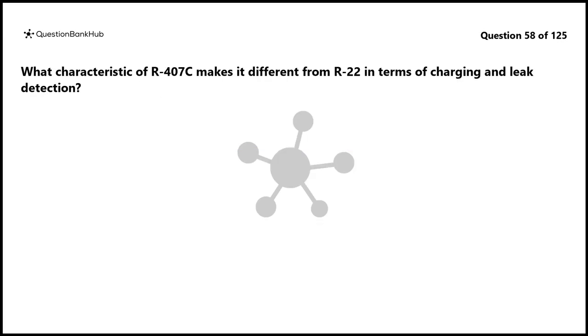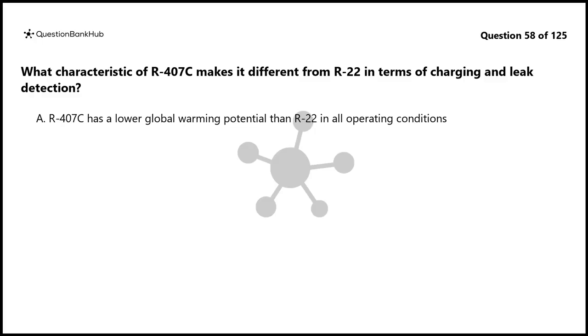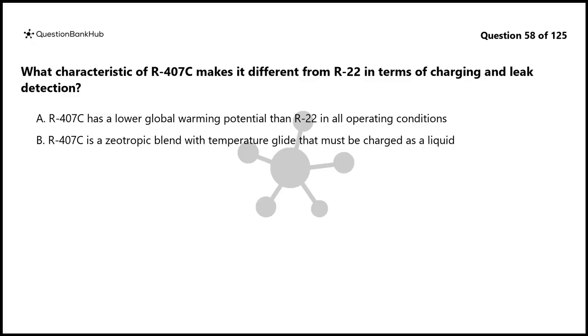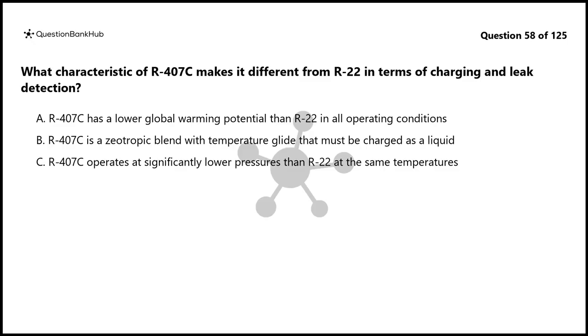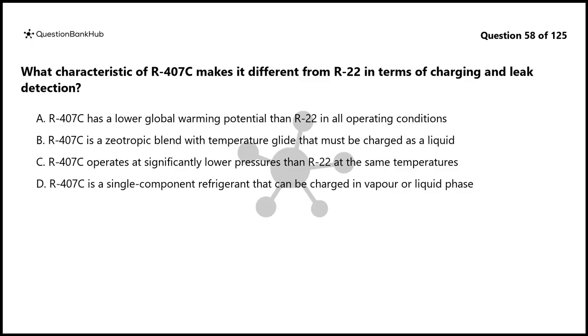Question 58. What characteristic of R407C makes it different from R22 in terms of charging and leak detection? A. R407C has a lower global warming potential than R22 in all operating conditions. B. R407C is a zeotropic blend with temperature glide that must be charged as a liquid. C. R407C operates at significantly lower pressures than R22 at the same temperatures. D. R407C is a single-component refrigerant that can be charged in vapor or liquid phase.